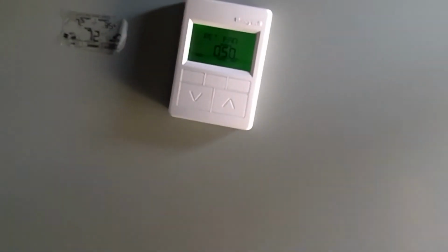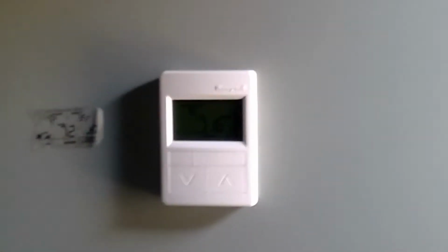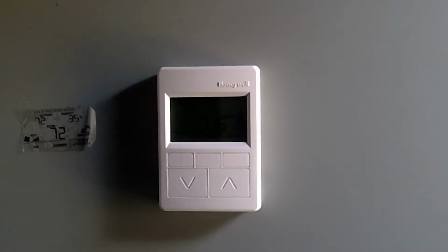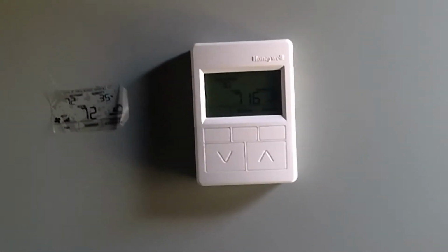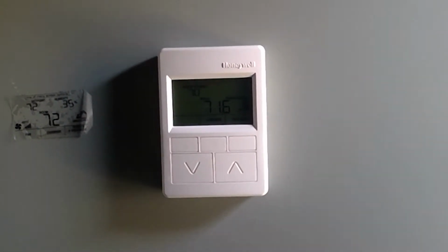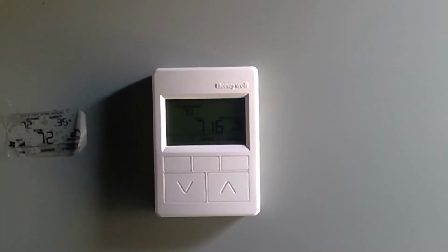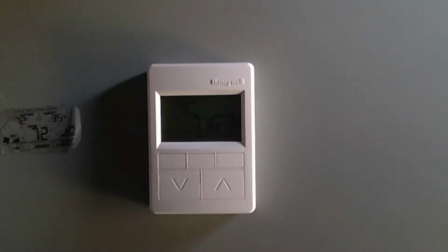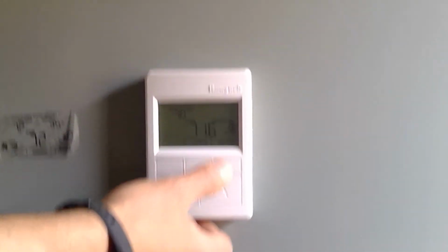Right, which you would, because we're negative, we're not raising positive, right? Yeah. So do we have to switch that? I think the operation of the damper is correct, because when it opens the damper, the fan speeds up. But when that damper downstairs closes, pressure drops for some reason. So it should actually want the damper to close. Yeah. But it's doing the opposite, right? So I don't know if you can reverse that stroke. Yeah, I'll reverse that. Okay. You know what I mean? Yeah, I do. Only because we're on a negative side, not a positive side.